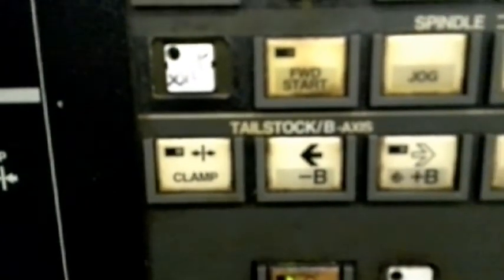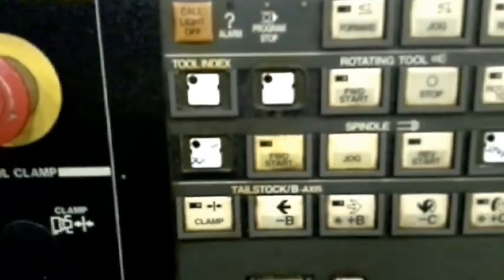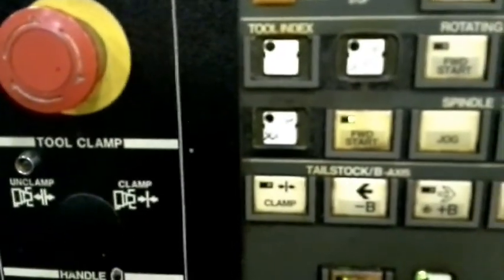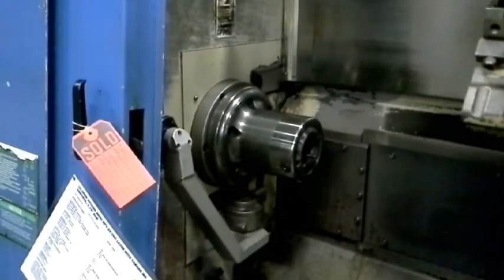I can put in M05 to stop. The spindle light goes out. I go to jog, spindle jog, spindle forward. The spindle forward light comes on, but the spindle is not running. And no alarm.